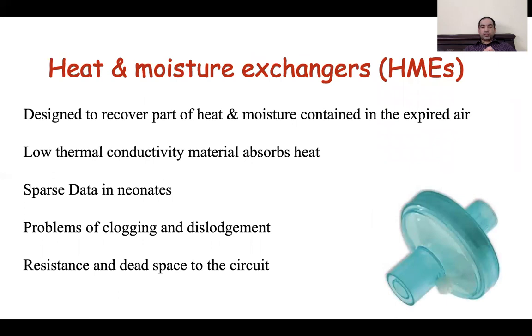Heat and moisture exchangers are also called artificial noses because they are designed to recover part of the heat and moisture from the expired air, which is then used for subsequent breaths during inspiration. They use low thermal conductivity material present inside plastic housing. They are predominantly used in pediatric and adult populations and the experience in neonates is very minimal. There are problems of clogging and dislodgement, which can lead to increased resistance and increased dead space in the circuit. Certain HMEs are covered with bacteriostatic material or come with bacterial and viral filters to decrease contamination.